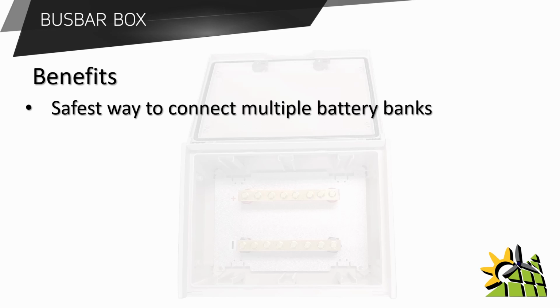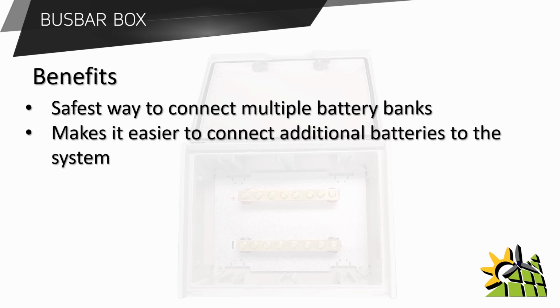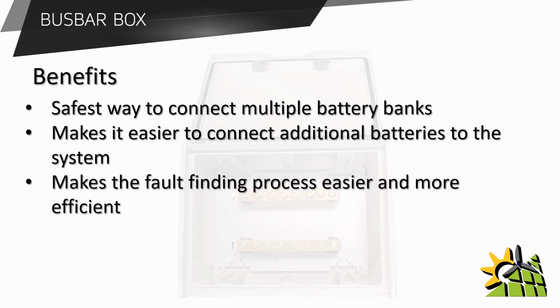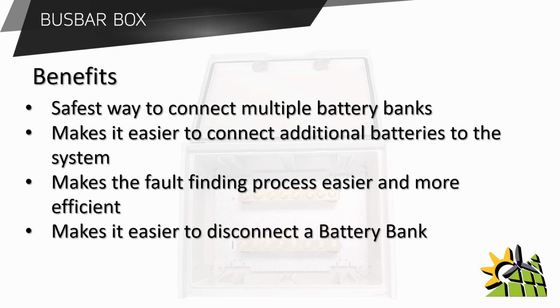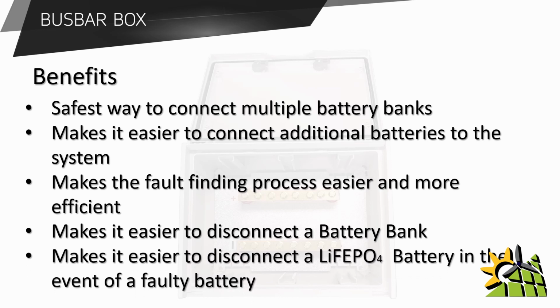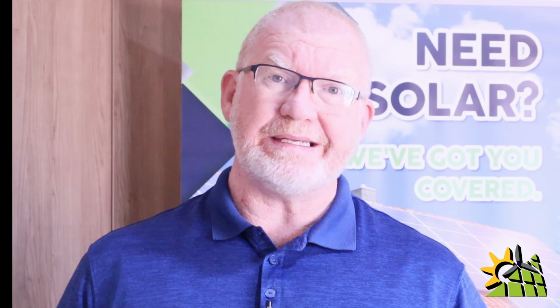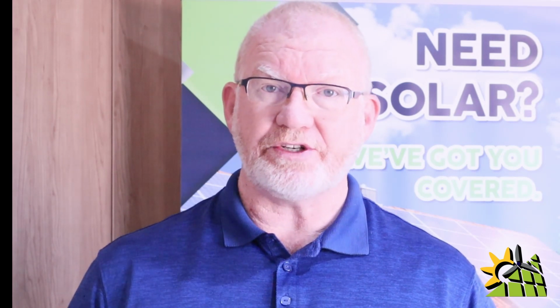It makes it easy to connect additional batteries to the current system. It makes the fault finding process easy and more efficient. It makes it easy to disconnect a battery bank if needed. And it makes it easy to disconnect a lithium phosphate battery if that battery were to become faulty. On an installation where there is more than one battery bank, it is essential that you install a busbar box, as it makes the installation safe, convenient, and far more efficient.